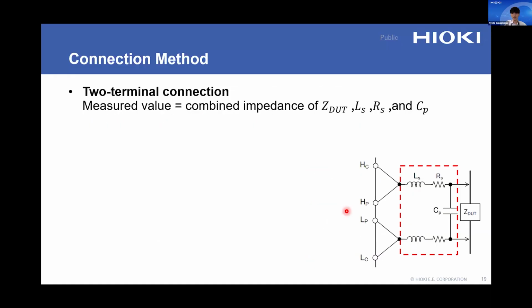There are several wiring methods, and I will introduce them one by one. First, here is the 2-terminal connection. In this method, the current and voltage paths are combined before reaching the DUT. In this configuration, parasitic capacitance, inductance, wiring resistance and contact resistance beyond the junction point are all included in the measured value. Although their effect can be reduced by the open short correction function, which I will explain later, some factors such as contact resistance vary with each probing and cannot be completely eliminated. Therefore, this method is suitable for measurement where the influence of parasitic impedance is small.